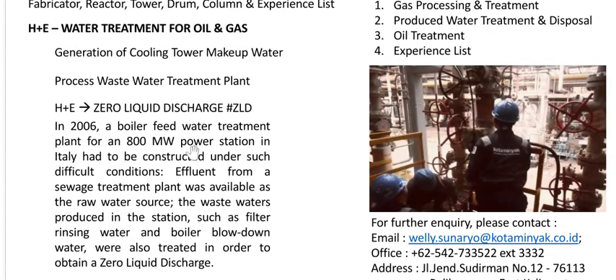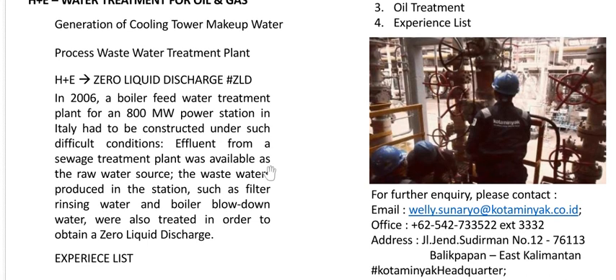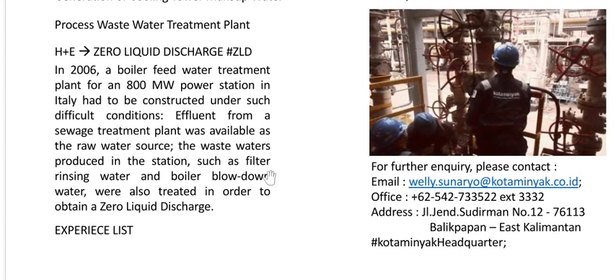In 2006, a boiler feed water treatment plant for an 800 megawatt power station in Italy had to be constructed under such difficult conditions. Effluent from a sewage treatment plant was available as the raw water source. The wastewater produced in the station, such as filter rinsing water and boiler blowdown water, was also treated in order to obtain a zero liquid discharge. And we also have seen the experience list of Hager-Elsasser.